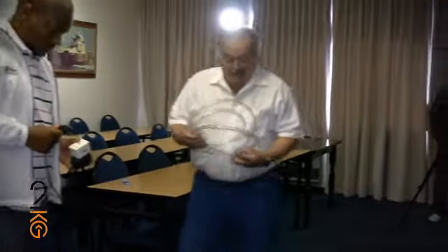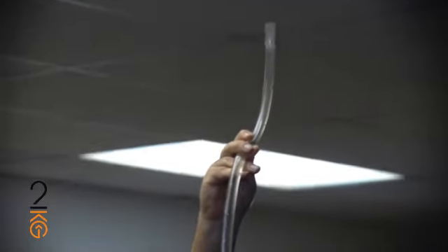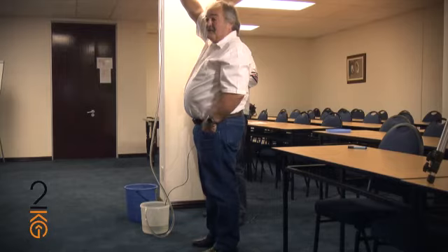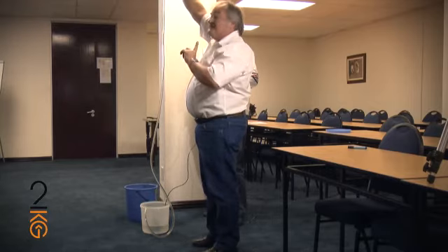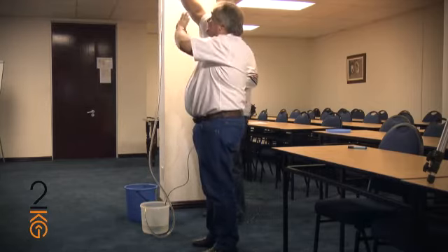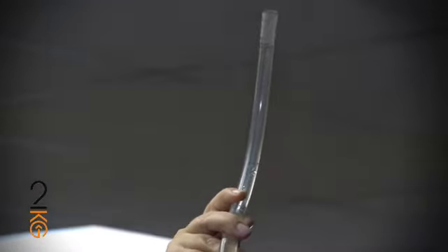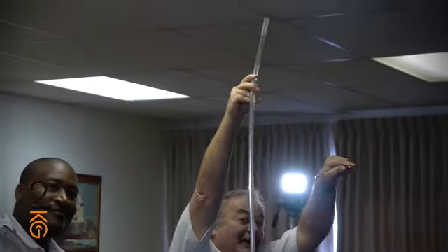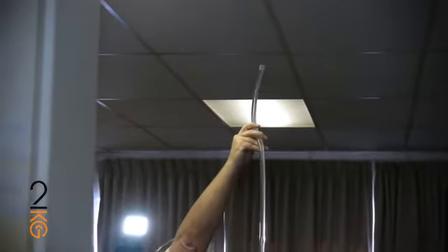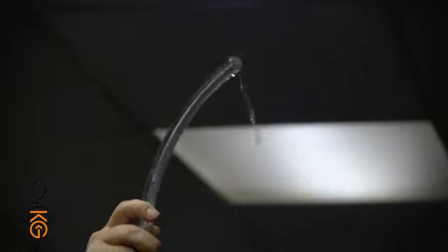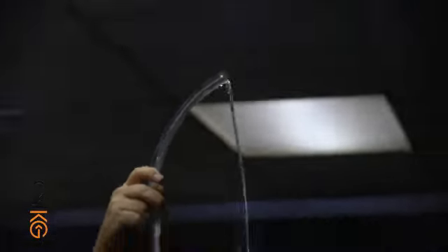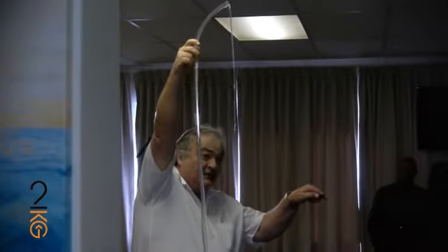Now, I'm going to connect some pipe to the pump. All right, can everybody see the level of water up there at the top? Now the pump is at shutoff head. So the pump is all the way onto the back side of the curve. Okay? We've got maximum head at zero flow. Now this pump just went from here back to here on the curve. If I lower this tube to here, now we're getting flow, so we've moved out to here on the curve.